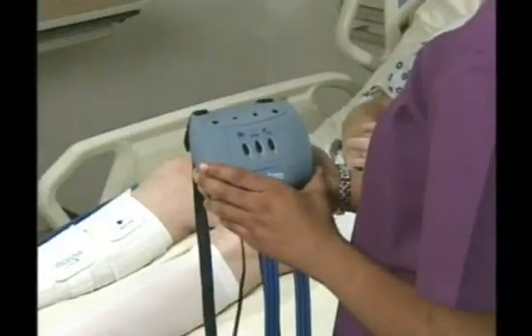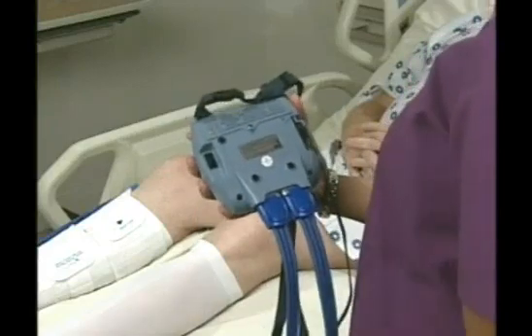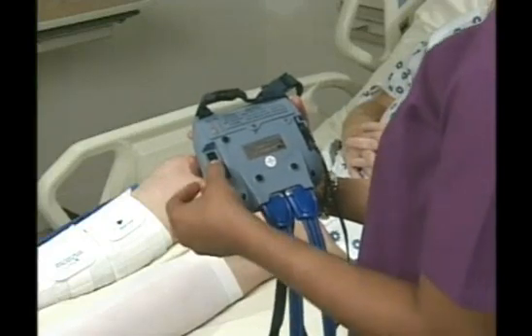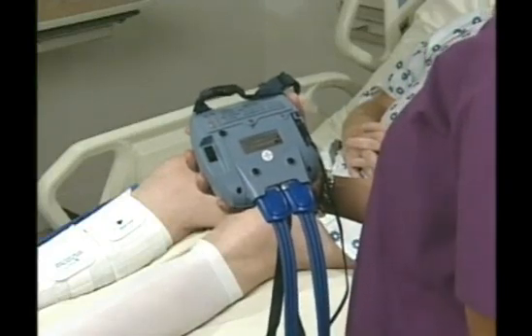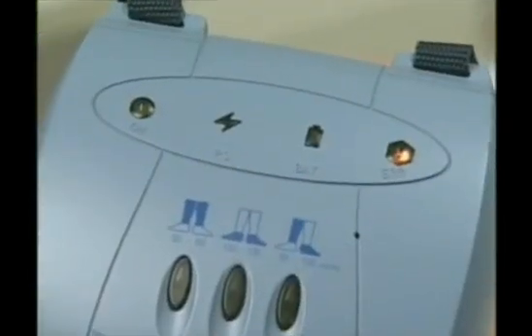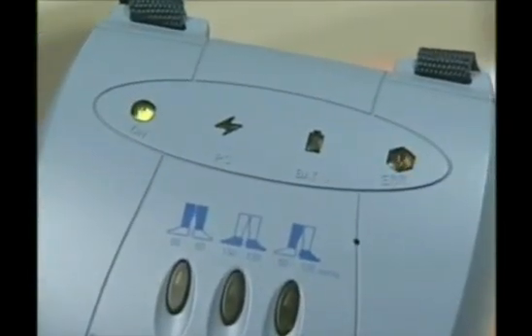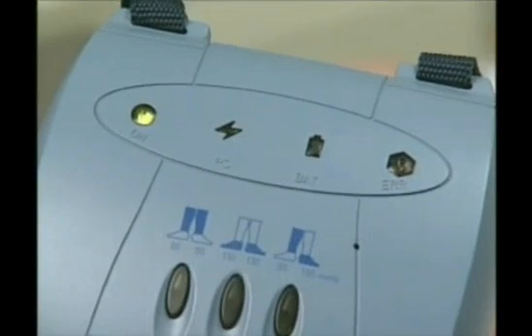Switch on the ActiveCare DVT unit's on-off control located on the back of the device to trigger the self-test mode. Both the power on and error indicators will flash, and the audio alarm will beep 3 times. The unit will then begin self-diagnostics. If any problems are detected, an alarm will sound. Refer to the troubleshooting section of the user manual to assist you in correcting alarm conditions.